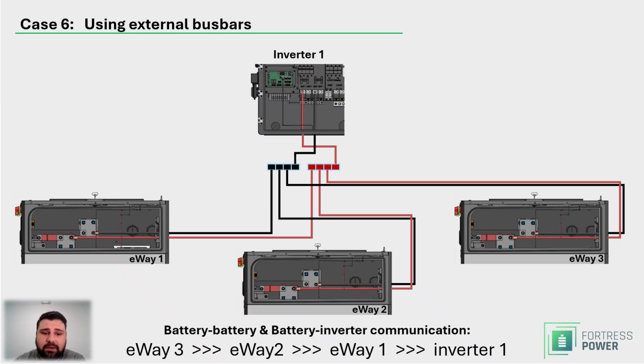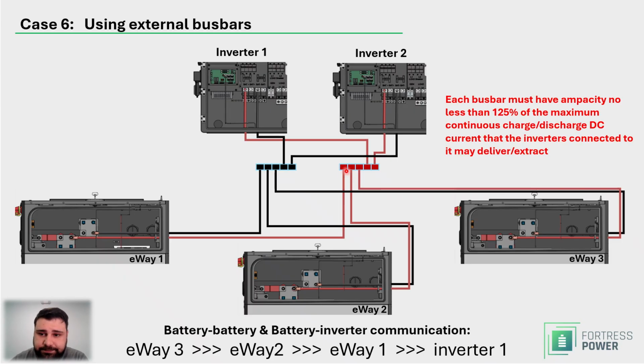If you were to have multiple inverters, again, now this is the case where the internal bus bars would not be enough. Let's say you have inverter 1 and inverter 2. eWay 1 connects to the positive and negative, eWay 2 does the same thing, and eWay 3 does the same thing, and the inverters connect to the same bus bars. So essentially, these DC bus bars create a common pool of energy that the inverters can take power from or add power to, so that the batteries can charge. And the communication is as follows: eWay 3, eWay 2, eWay 1, and then from eWay 1 to inverter 1. Again, because this is a shared DC bus bar. It's not like the previous case when you had each inverter having its own group.